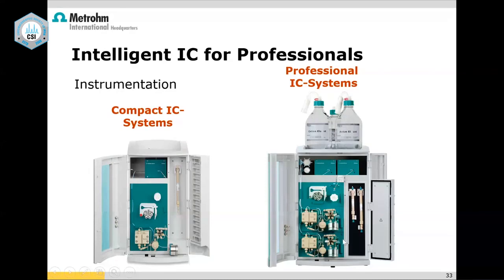This is basically a dual channel, the highest end system, which can be used for simultaneous anion and cation. That is possible. Suppose you want to run a gradient, that is changing the concentration of the eluent with respect to time. So we can combine these two pumps and run a high pressure gradient for anion analysis or cation analysis. That is possible with this system.